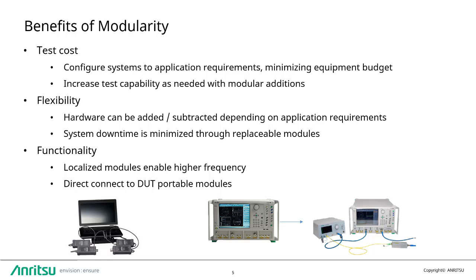This is especially valuable for high-mix testing areas like research and development labs, where a wide variety of DUTs are tested. Replaceable modules also increase uptime as faulty system components are more quickly replaced to keep the system up and running, compared to integrated VNAs, which must be taken offline and fixed as a unit.